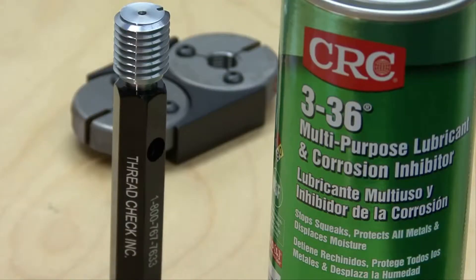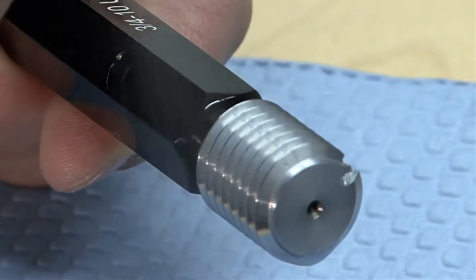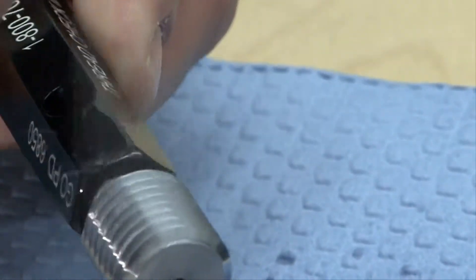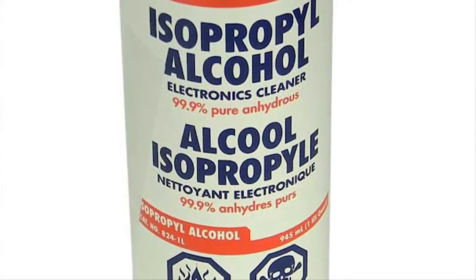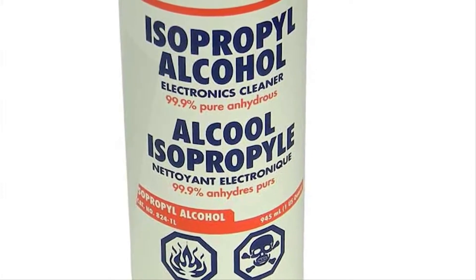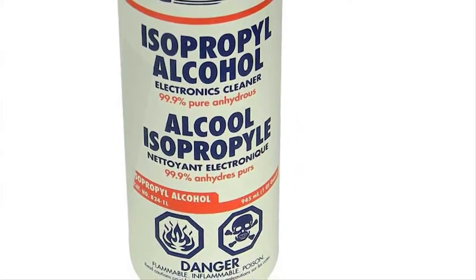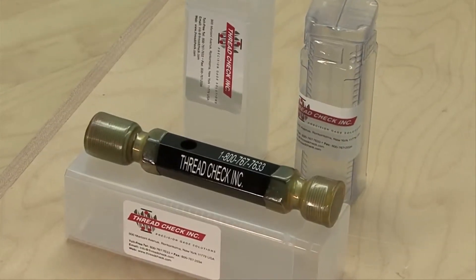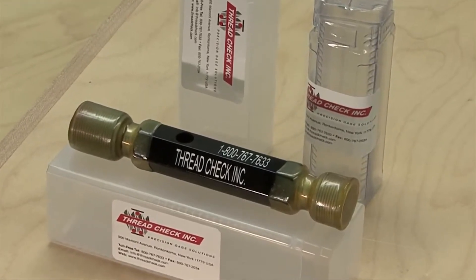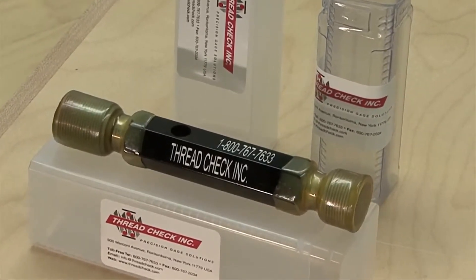Thread plug gauges should be cleaned with solvent or air and then frequently re-coated with a rust preventative. In clean room environments, isopropyl alcohol may be substituted to help reduce friction on the gauges. Thread plug gauges should be protected in plastic tubes and coated in wax when not in use to prevent nicks to the threads.